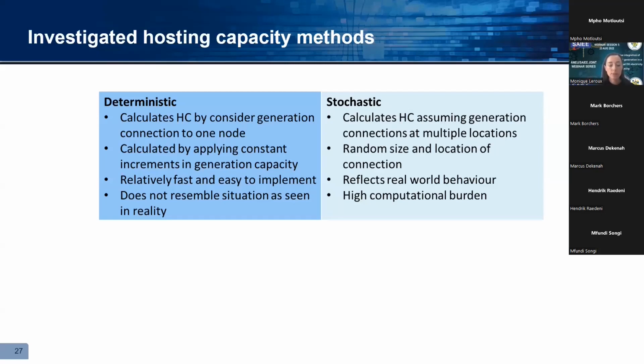And then the other method, which we also developed a tool for, is to calculate the hosting capacity where you assume that there are multiple generators connecting at different locations, and then increasing the size of those generators across a range with set increments, and then seeing where voltage and thermal violations happen. This more closely reflects what's happening in the real world, because on your network you would typically not only have one generator at one bus, but you would rather want to look at a situation where there are multiple generators being integrated onto your system, and try and understand how that's going to impact your system. But for this method, obviously via computation, it would take a bit longer to calculate.